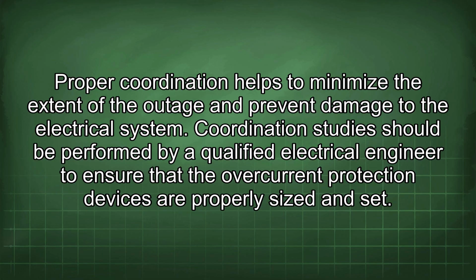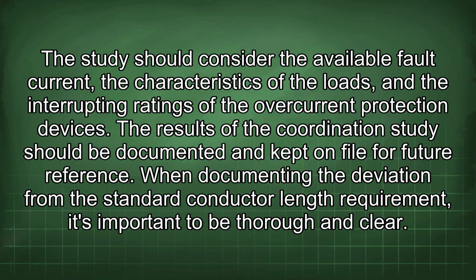Coordination studies should be performed by a qualified electrical engineer to ensure that the overcurrent protection devices are properly sized and set. The study should consider the available fault current, the characteristics of the loads, and the interrupting ratings of the overcurrent protection devices. The results of the coordination study should be documented and kept on file for future reference.